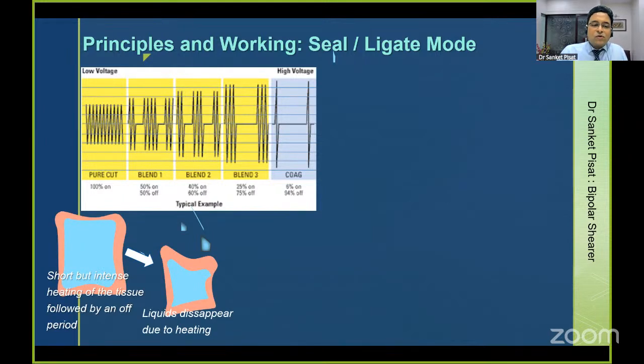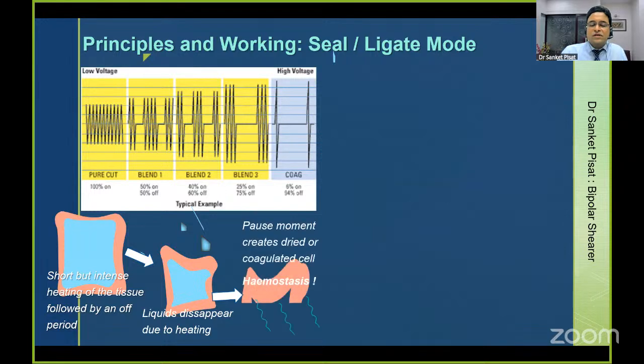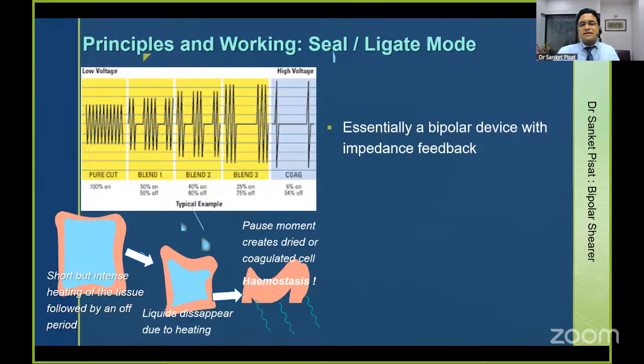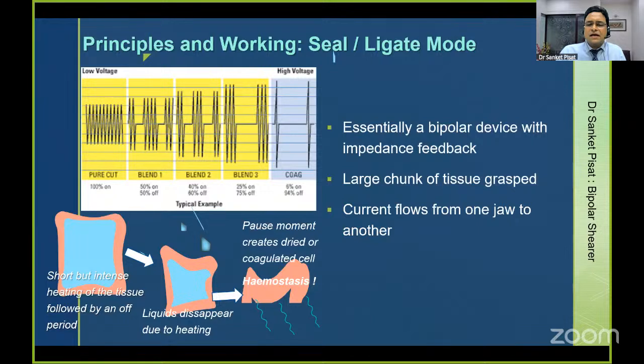So you already know the concept of how coagulation and cutting occur. So what exactly is this shearer, as we call it? It is essentially a bipolar device with an impedance feedback. That means the machine understands when a critical limit of tissue resistance is reached. A large chunk of tissue can be grasped. The current will flow from one jaw to another.